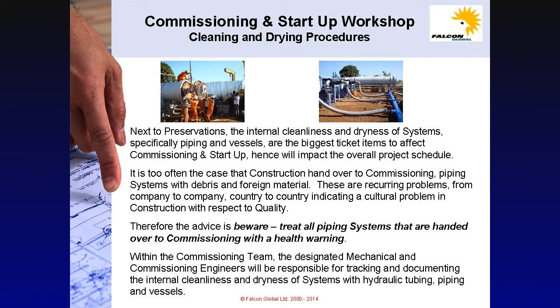Next to preservations, the internal cleanliness and dryness of systems, specifically piping and vessels, are the biggest ticket items to affect commissioning and startup, hence will impact the overall project schedule. It is too often the case that construction hand over to commissioning piping systems with debris and foreign material. These are recurring problems from company to company, country to country, indicating a cultural problem in construction with respect to quality. Therefore, the clear advice on this course is beware. Treat all piping systems that are handed over to commissioning with a health warning.